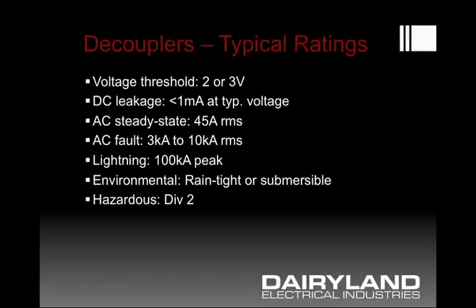The AC steady state current that can flow through the product being mitigated continuously is commonly in the neighborhood of 45 amps AC RMS, and the typical fault rating of the device is in the several thousand to perhaps 10,000 amp range.